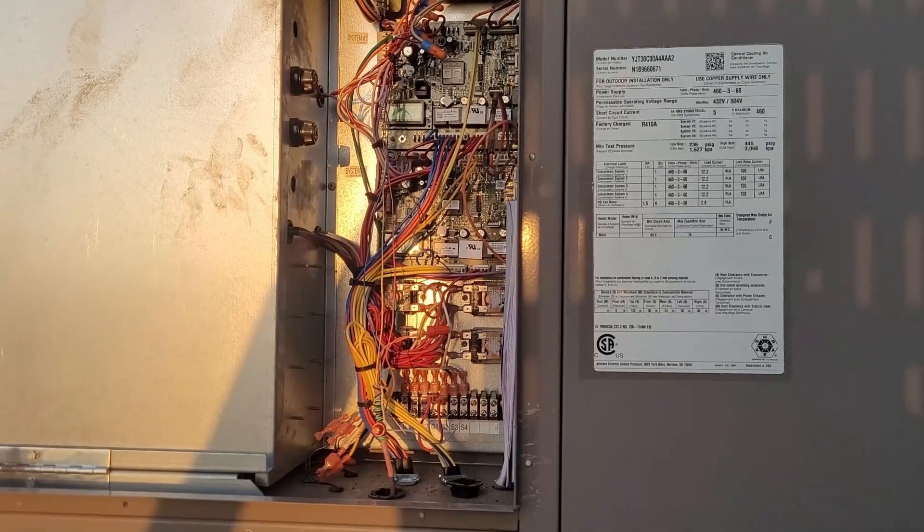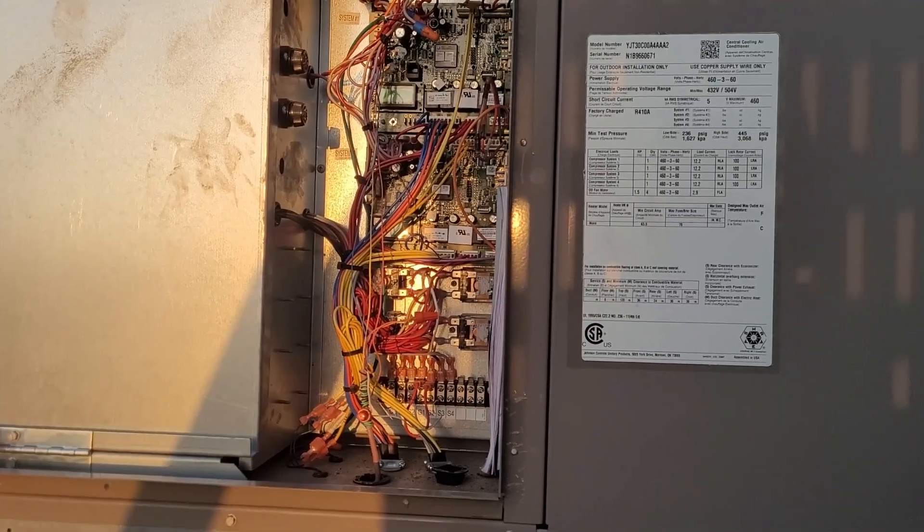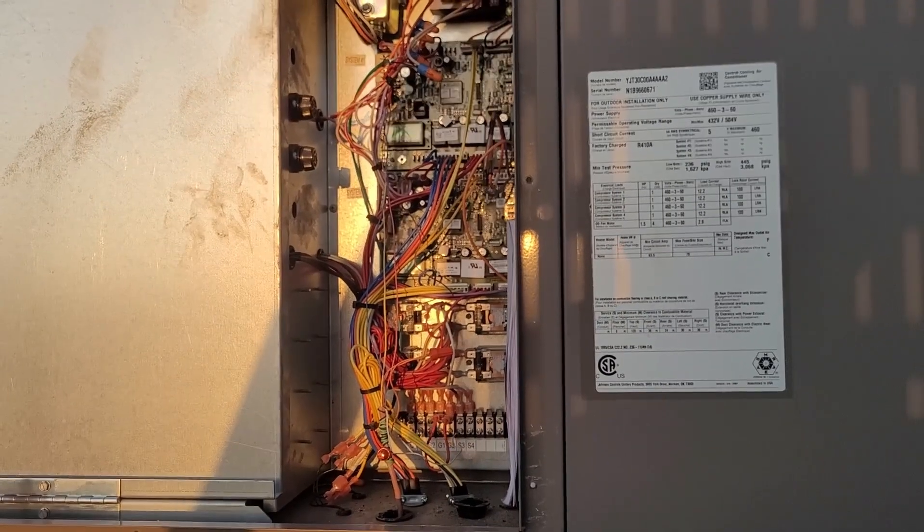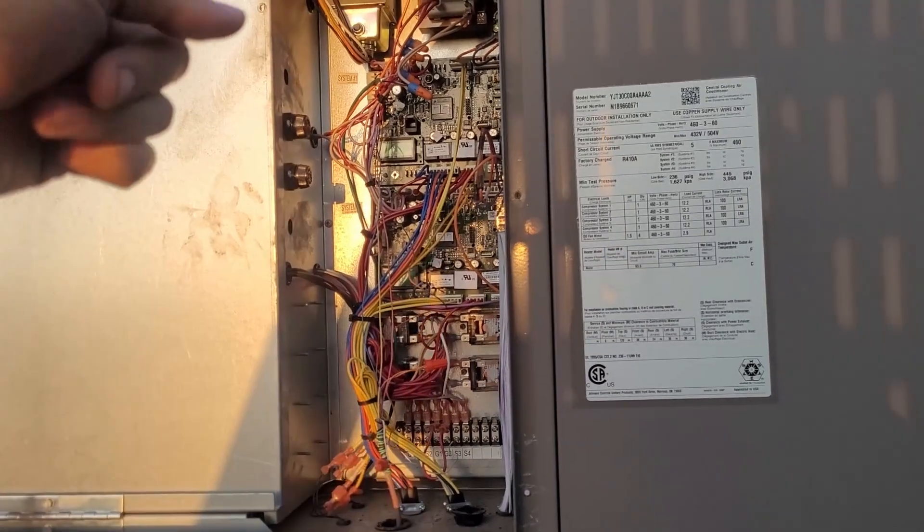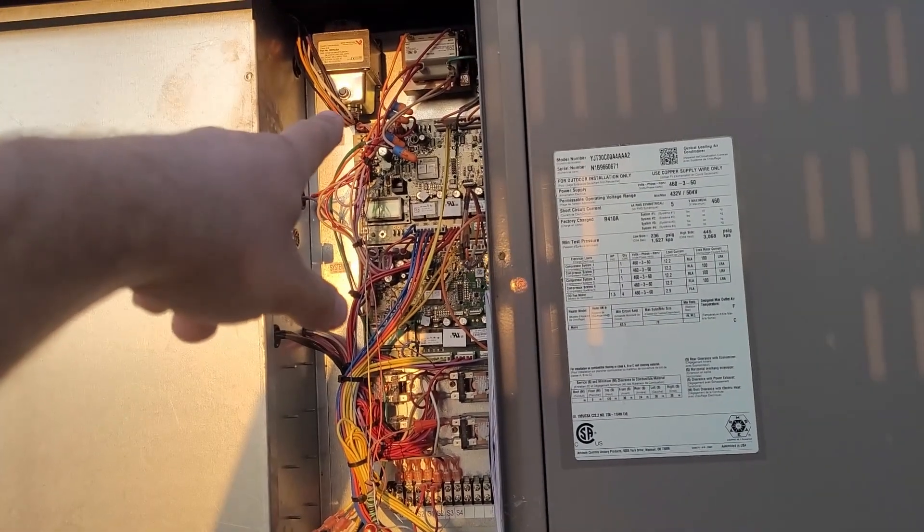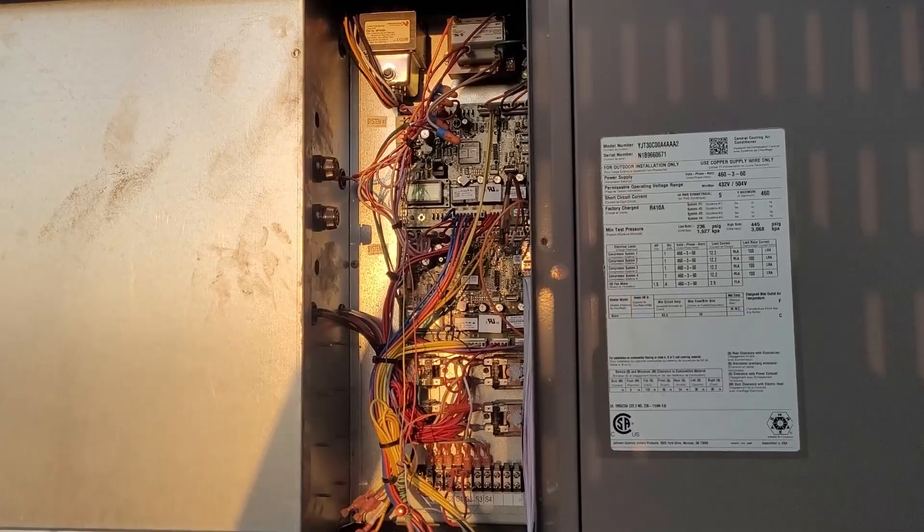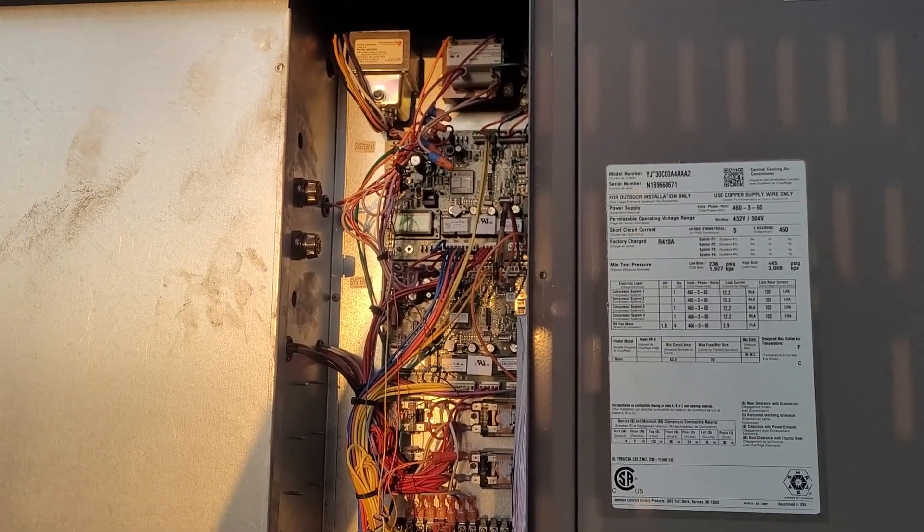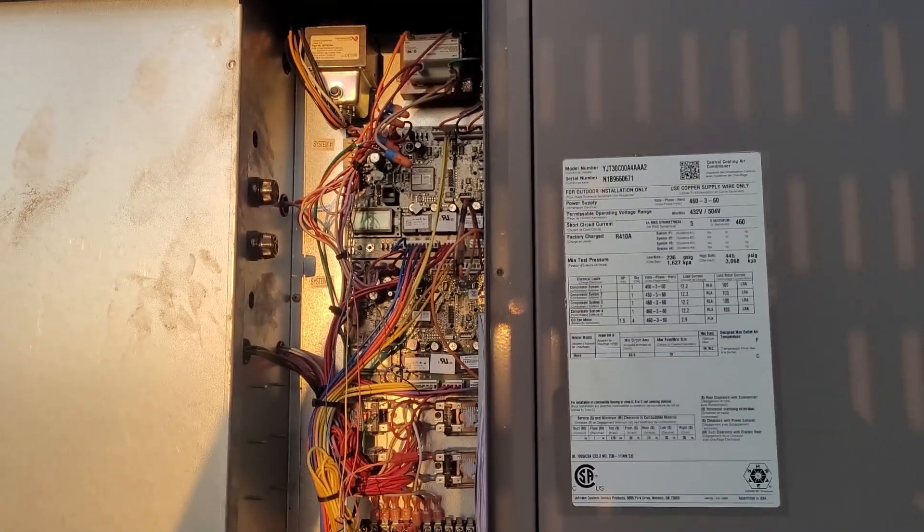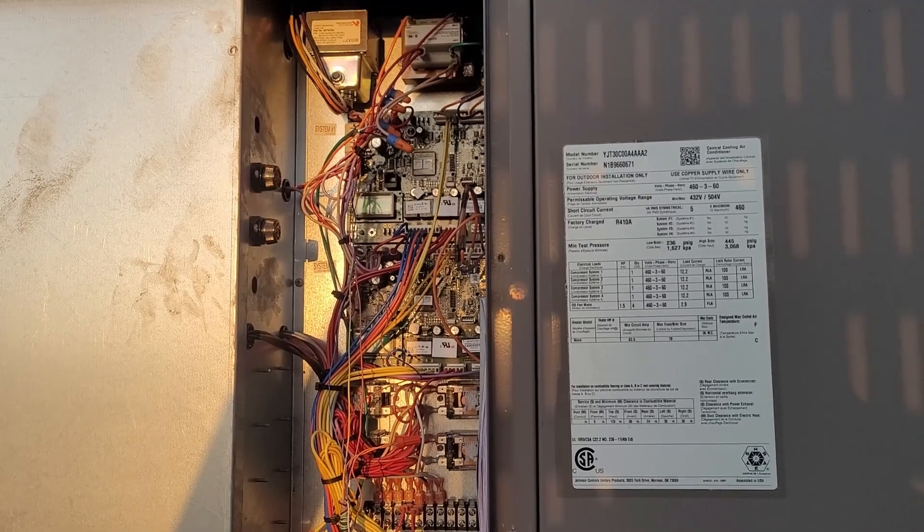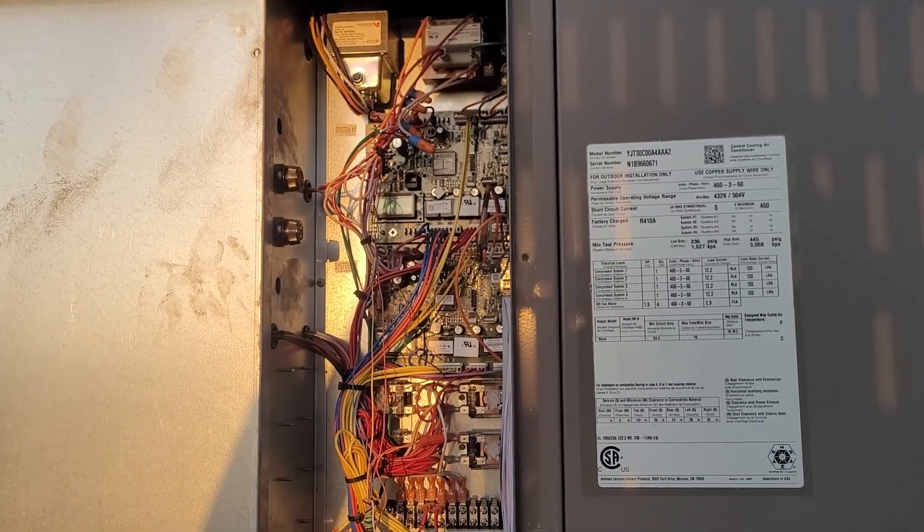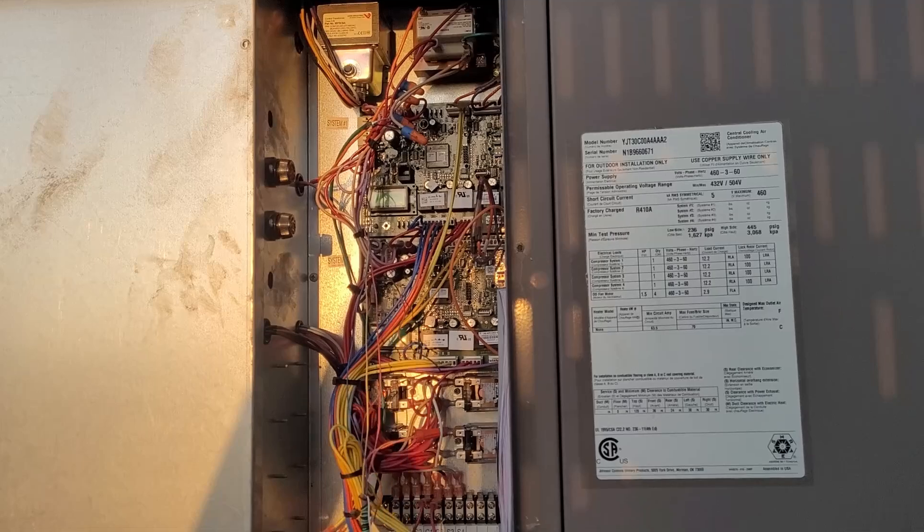And then S1 and S3 go down and keep the liquid-line solenoid valves open and also back-feed back into these thermostat terminals, these Y terminals. So you have like a death loop. So as soon as you engage it, it never shuts off. And that's what we were experiencing. The coils would freeze and we'd get low-pressure alarms.